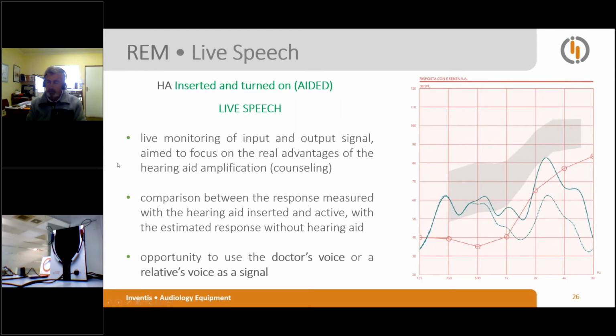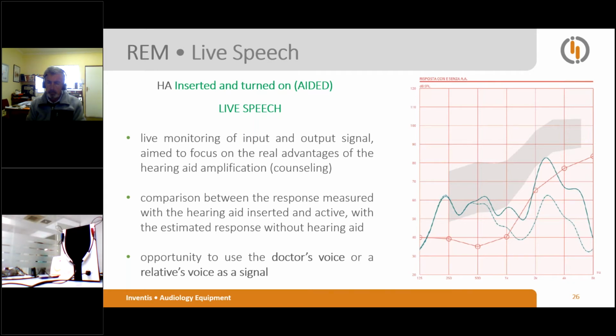Okay, live speech. It could be particularly useful for the patient and for others to observe how the use of a hearing aid can improve the patient's hearing. For this purpose, the live mode within Maestro allows the hearing care professional to obtain this measurement. This test mode has a counseling purpose.